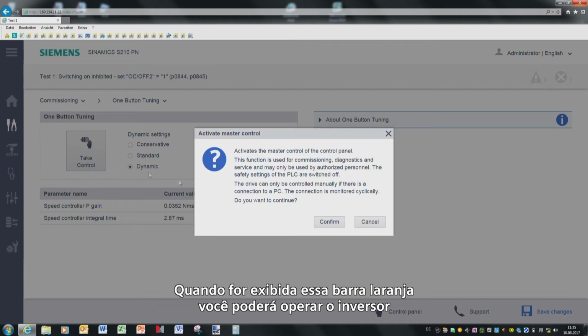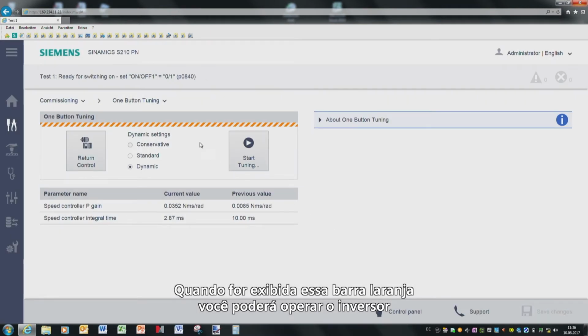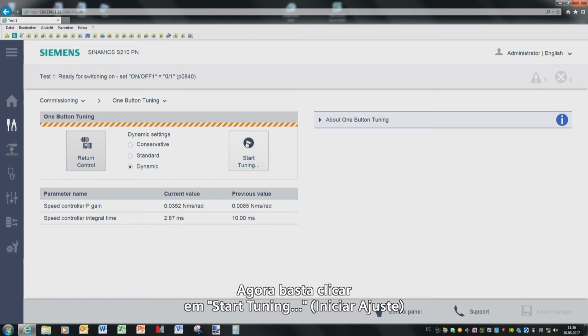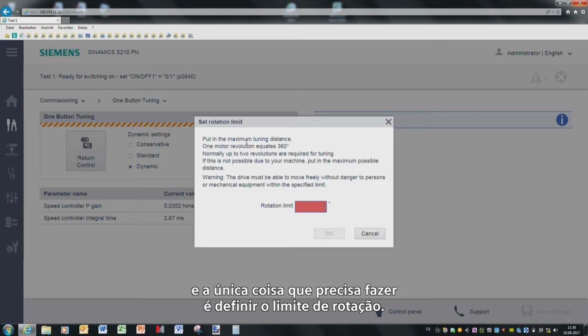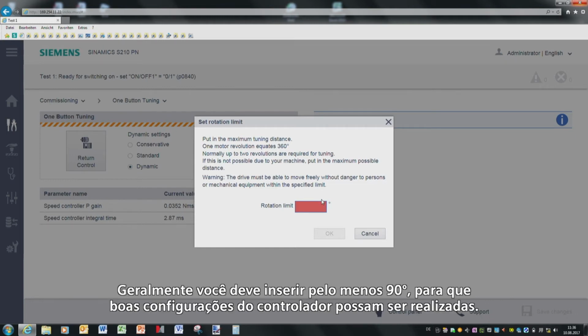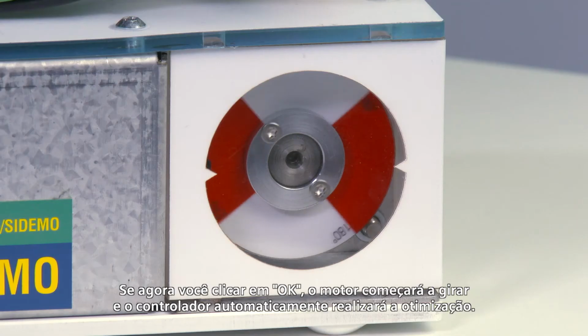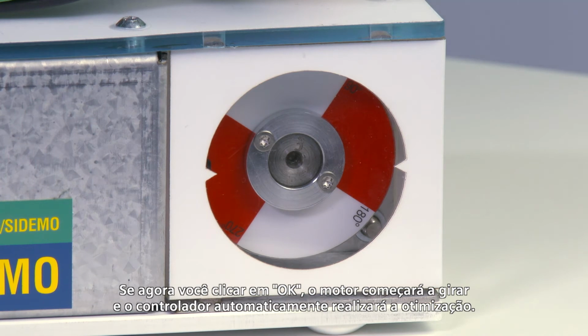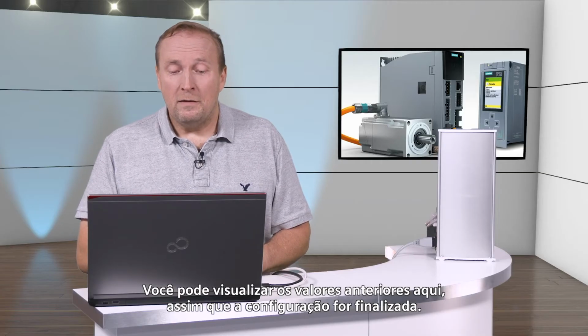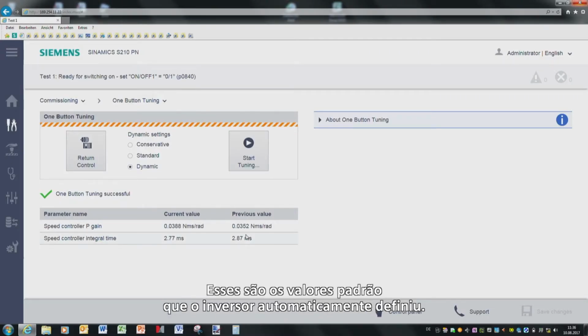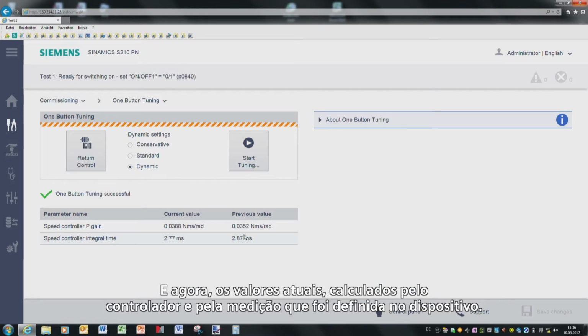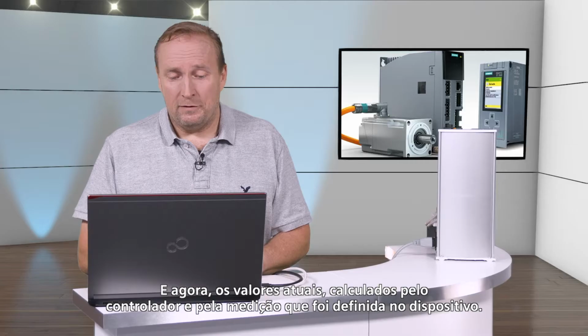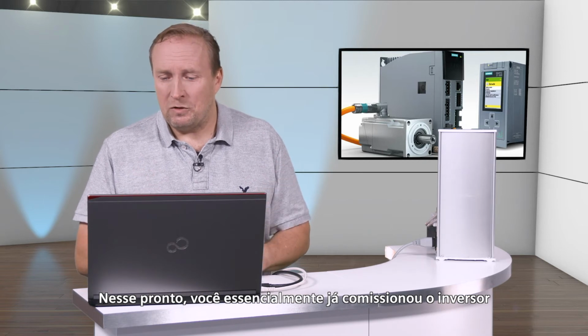Once you see this orange bar, then you can operate the drive. You now simply go to Start Tuning, and the only thing you have to do is set the rotation limit. Typically, you must enter at least 90 degrees so that a good controller setting can be achieved. If you now click OK, the motor starts to rotate, and the controller automatically optimizes itself. You can see the previous values here once the setting has been made. These are the default values that the converter automatically sets. And now also the actual values that were calculated by the control and the measurement and have been set in the device. At this point, you have essentially commissioned the drive.